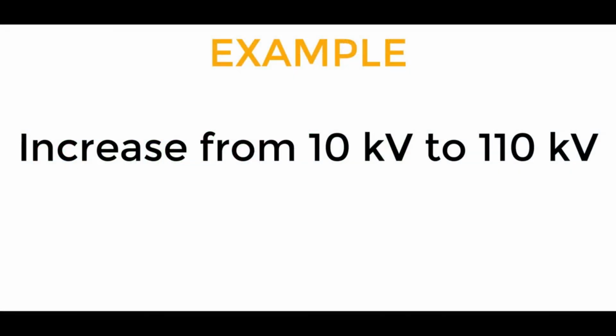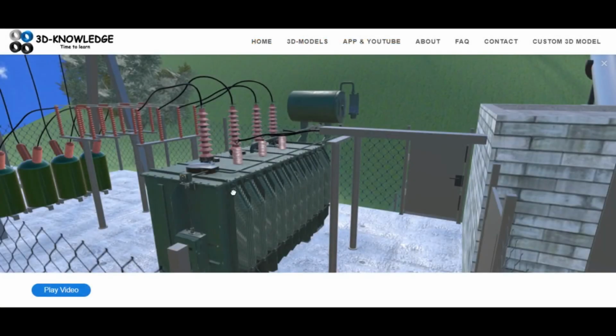Probably going to increase it to, for example, 110,000 volts. You need to increase the voltage because if you don't, you're going to need huge cables to transfer that amount of power. So you step up the voltage in order to reduce the current. Now there's a relationship between power, current, and voltage.